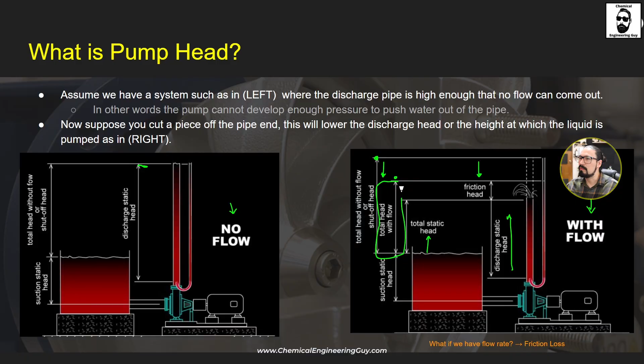Then we have the total head with flow. This is the one reported with the friction and the total static head. Now, what's the only difference between this part and this part? There will be a decrease because there's flow rate. But not only that - if you want to calculate the total static head and the friction head, that will give you exactly the total head with flow. That's the general idea I want to present in this slide.